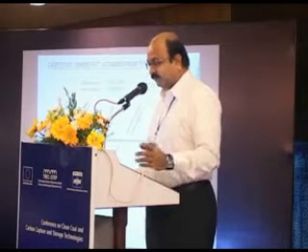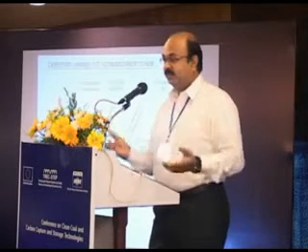So this was the unit when it was designed in 1982, and when we actually went to study what was happening, this was the scenario, and that led to making the specifications to make the boiler up to 215 megawatt, and all the changes. Basically, boiler efficiency is down by 5%, 5-6% straight. Turbine side you are increasing. So overall, it's going to probably bring about an 8 to 10% net effect. I'm not talking percentage points, 32 becoming 42, but straight away 32 becoming 35, or 29.5 becoming 32. So that's about 10% increase and 10% reduction in the emissions every second that boiler will run. So that's the part we are driving.